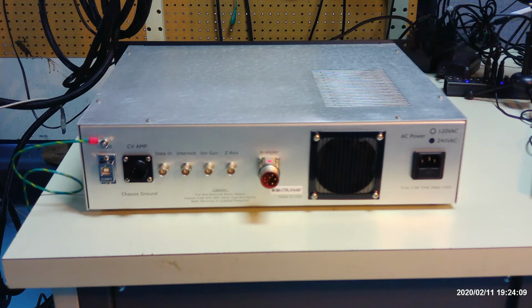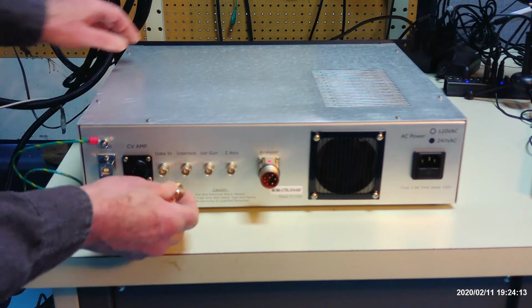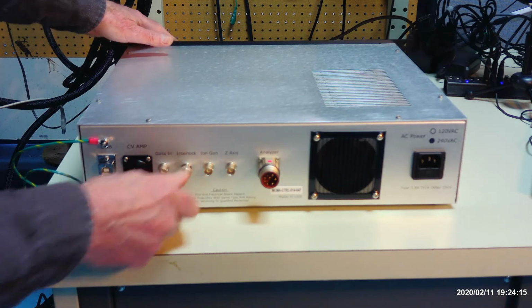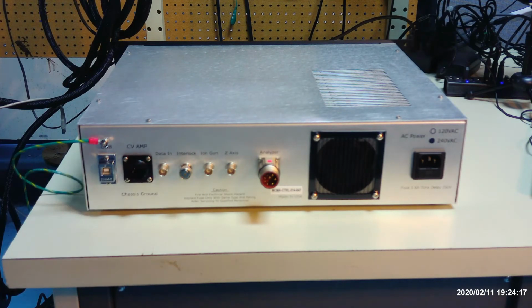If you don't have an ability to connect it to your ion gauge set point, then we also provide a shorting cap. You can put the shorting cap on, and that will bypass the interlock. You want to make sure, however, when you operate the microCMA controller, that your vacuum is at least in the low 10 to the minus 7s. Preferably, since Auger is a UHV technique, you want to be in the low 10 to the minus 9s or even the 10 to the minus 10 torr.